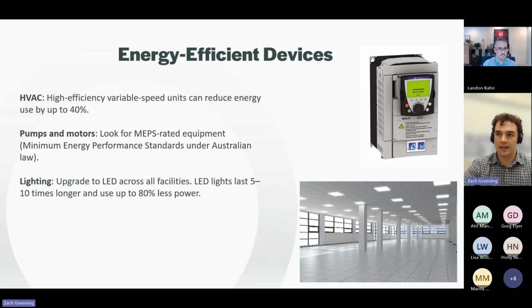So think of it as a dimmer control for a fan, and buildings tend to have lots of fans, although you don't see too many of them. VSDs can offer up to a 40% reduction in HVAC energy use, which is significant. It can help reduce your peak demand contribution, and a lot of them will qualify for New South Wales energy saving schemes incentives. Full VSD upgrades can also help improve your NABERS energy rating, maybe by half a star to a full star, depending on baseline performance.